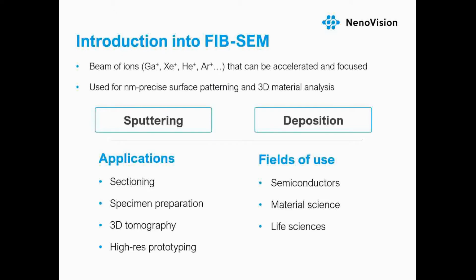Focused ion beam sources coupled with scanning electron microscopy have drawn significant interest due to their unique ability to generate a variety of structures, whether through milling or ion beam induced deposition, while being directly observed via SEM. Focused ion beam generally consists of an ion source, a series of electrostatic lenses to shape the beam, and a scan generator to guide the beam onto a sample with a moving stage. In a typical dual platform instrument, an electron column is mounted vertically and the ion column is mounted at an oblique angle, normally between 45 to 55 degrees.